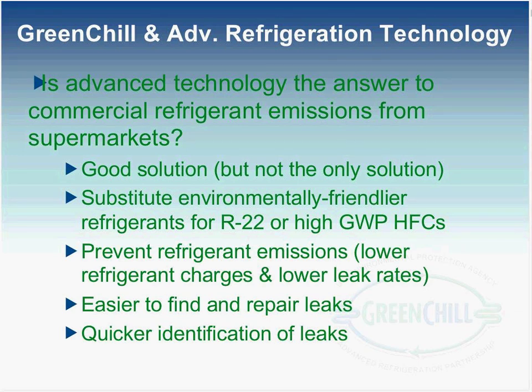The reason we think advanced refrigeration technology is a very good solution is because it enables supermarkets often to substitute environmentally friendlier refrigerants for the more traditional refrigerants that are normally used in standard stores. And the main reason is because a lot of advanced refrigeration technologies prevent refrigerant emissions. Whenever you can prevent emissions, it's certainly always better than repairing emissions because, by definition, if you're repairing it, that means that a certain amount has already harmed the environment. So we certainly prefer prevention over repair.